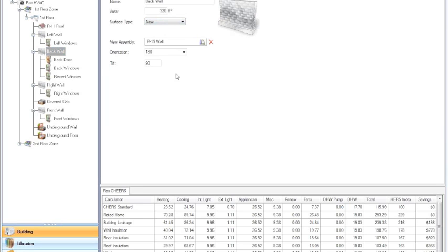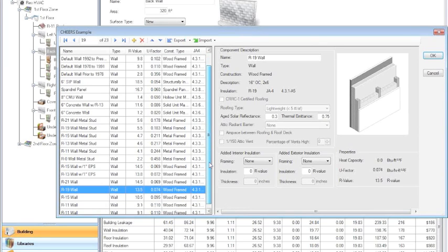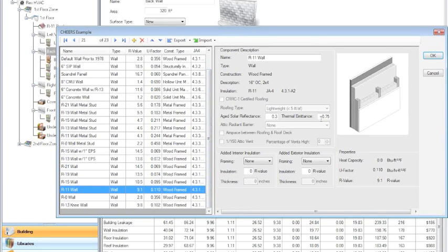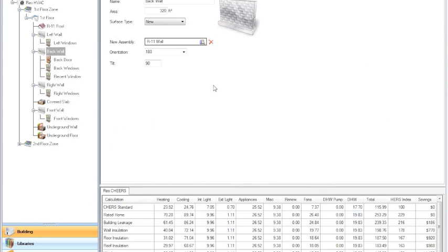So now you specify that that's existing, and let's say that wall was built fairly recently. That's a new R11 wall. Now EnergyPro, when it looks at wall upgrades, will ignore that wall in the list. So that's the use of new. Normally everything will be existing, but if you've got anything you want to say is off the table for upgrades, then set it to new.